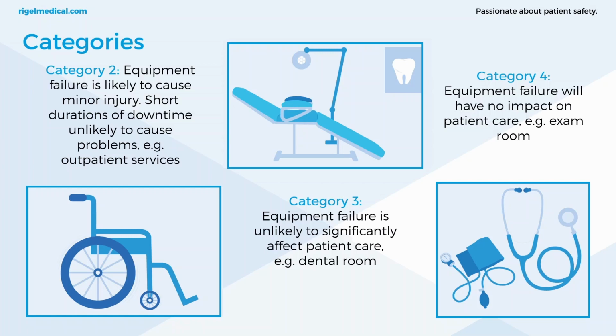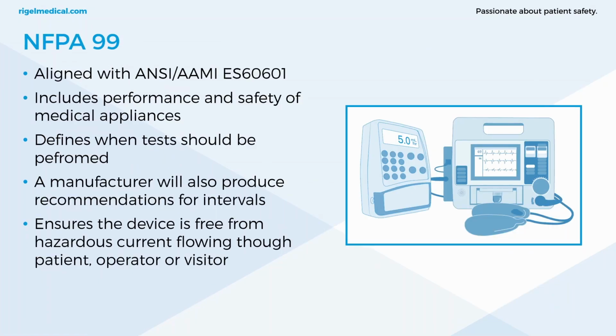All areas in a facility must have a risk assessment. That is an absolute necessity. Categorisations do have an impact on safety testing. So for example, some electrical safety tests are actually omitted from category 3 and category 4 areas. So you don't need to perform specific tests in these particular areas. So these categories are important to understand for electrical safety.